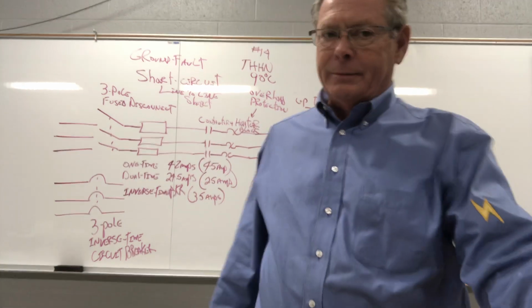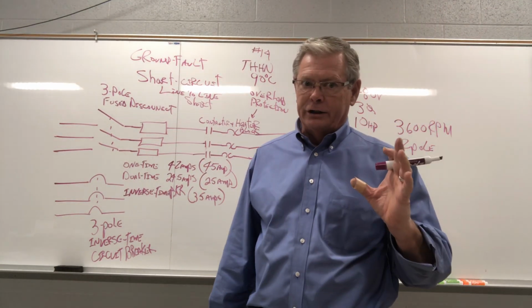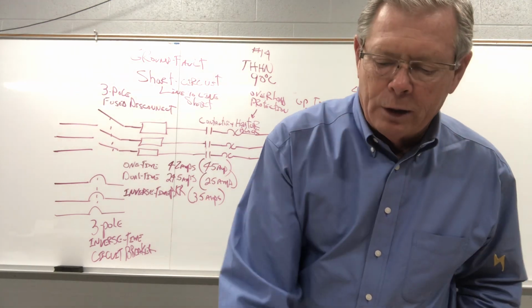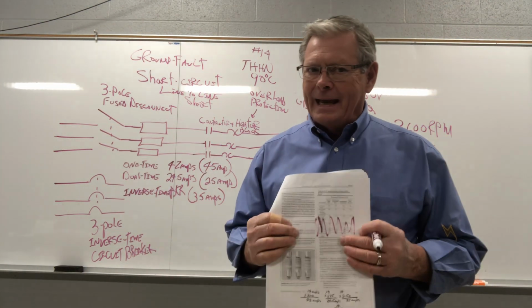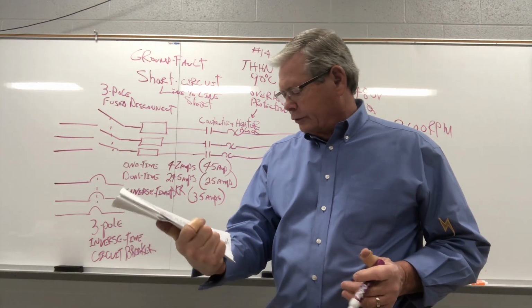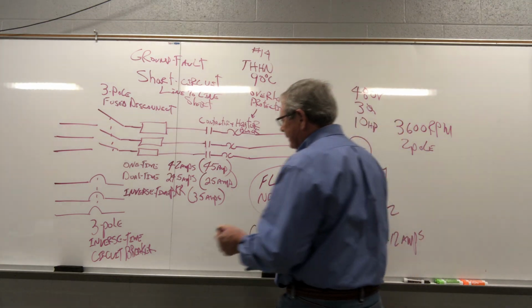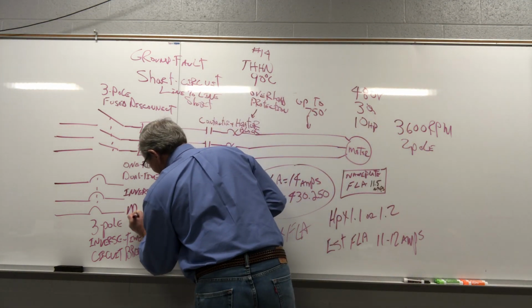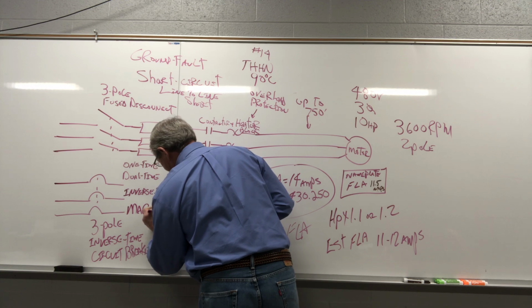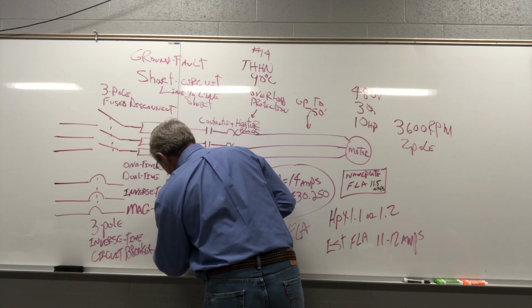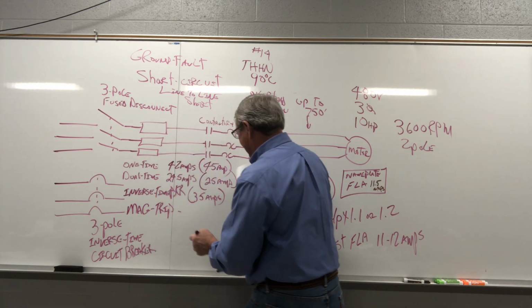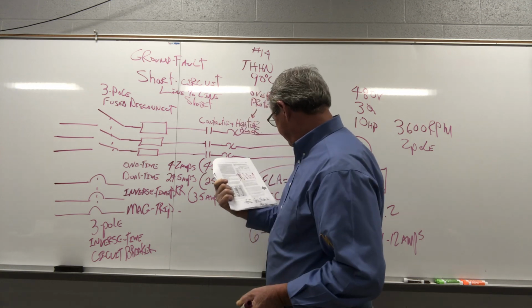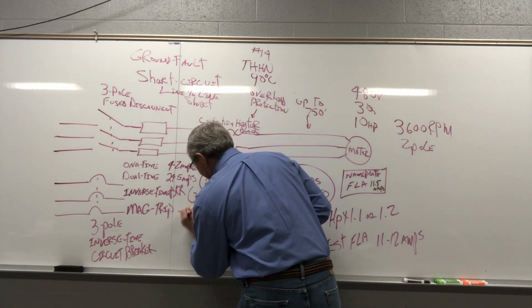A magnetic trip doesn't have to heat up. It just looks for that current spike. So the multiplier for it is 800%. So we take 14 times 800%, and that's mag trip or instantaneous trip, same thing, and that is 112 amps.